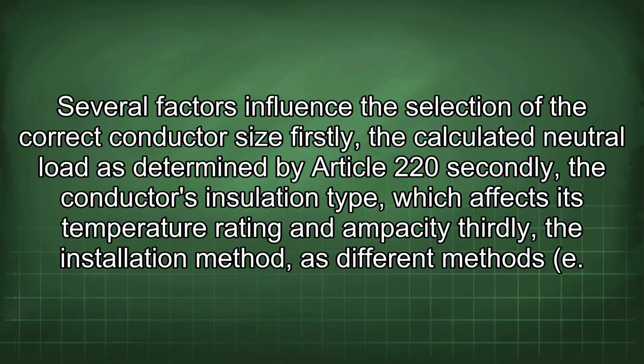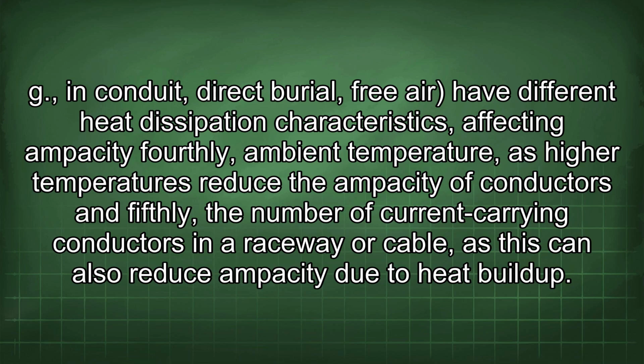Several factors influence the selection of the correct conductor size. Firstly, the calculated neutral load as determined by Article 220. Secondly, the conductor's insulation type, which affects its temperature rating and ampacity. Thirdly, the installation method, as different methods, e.g. in conduit, direct burial, free air, have different heat dissipation characteristics affecting ampacity. Fourthly, ambient temperature, as higher temperatures reduce the ampacity of conductors. And fifthly, the number of current carrying conductors in a raceway or cable, as this can also reduce ampacity due to heat buildup.